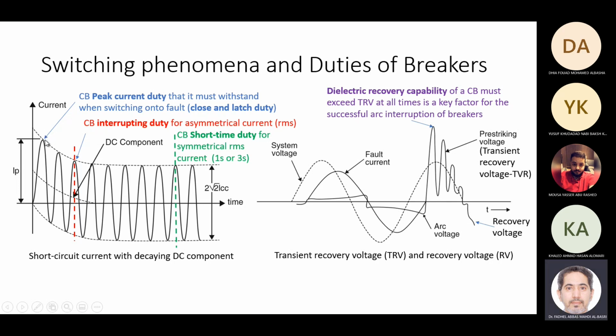So we have different ratings. One of the ratings is that it must be able to close into faults. While you are closing a breaker there may already be a fault, so it should handle this high current. We call it the peak current duty, or the close and latch duty of the breaker. The breaker manufacturer will give you this, in kiloampere peak. It's the maximum peak current after half a cycle that the circuit breaker can handle. So each breaker has its maximum peak current that it can handle.